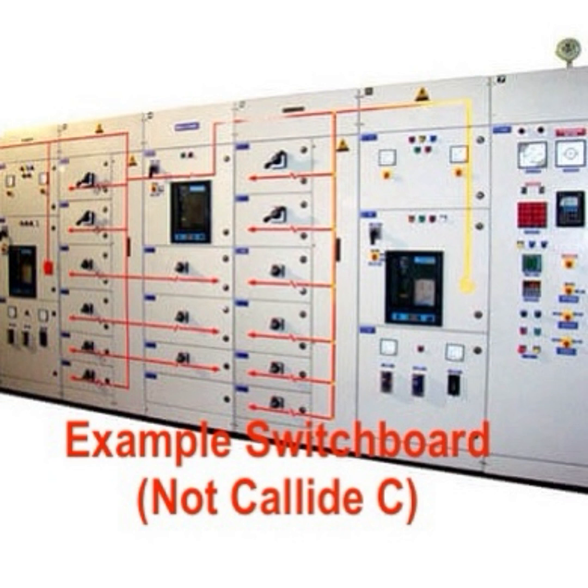Protection circuit breakers often have two sources of DC supply for redundancy, commonly referred to as their X and Y circuits. In the case of the generator circuit breaker that connected the generator to the grid, the X supply came from Unit C4's DC main switchboard, and the Y came from Unit C4's DC distribution board. Had the ACS changed over, the Y circuit would have been live and then allowed the GCB to operate if needed. And here's my quandary.